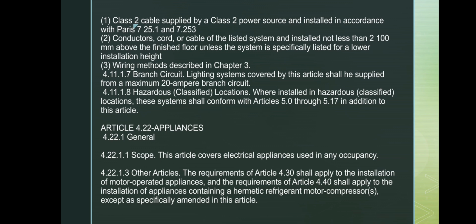517. The next article we must tackle is Article 422, which covers electrical appliances. It states that all appliances are covered by this article unless otherwise specified. Motor-operated appliances follow Article 430, while appliances using refrigerant compressors follow Article 440 unless modified by Article 422.